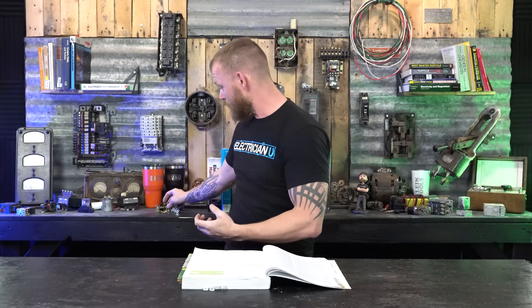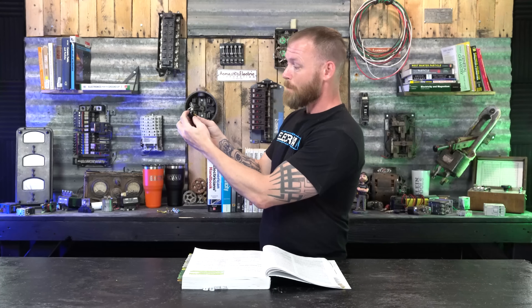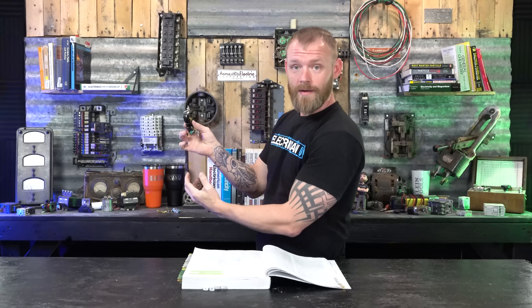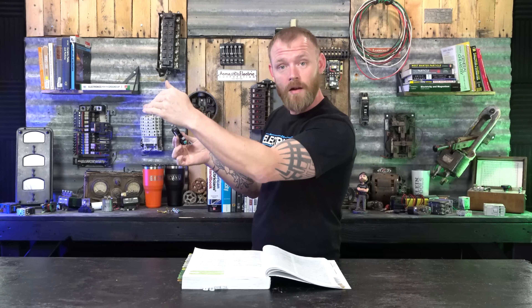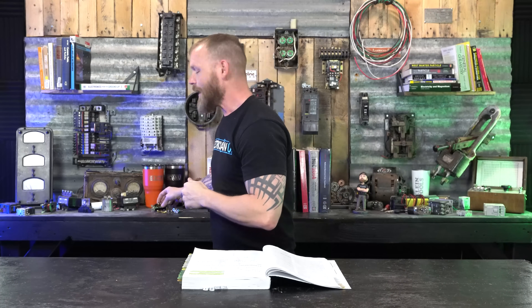So with 21 amps being drawn on a 15 amp receptacle, the metal inside is only rated for 15 amps. Over a long period of time, 21 amps is going to heat that metal so much that it starts melting the plastic around it — and the breaker is never going to trip because you're not hitting that 130 percent threshold.